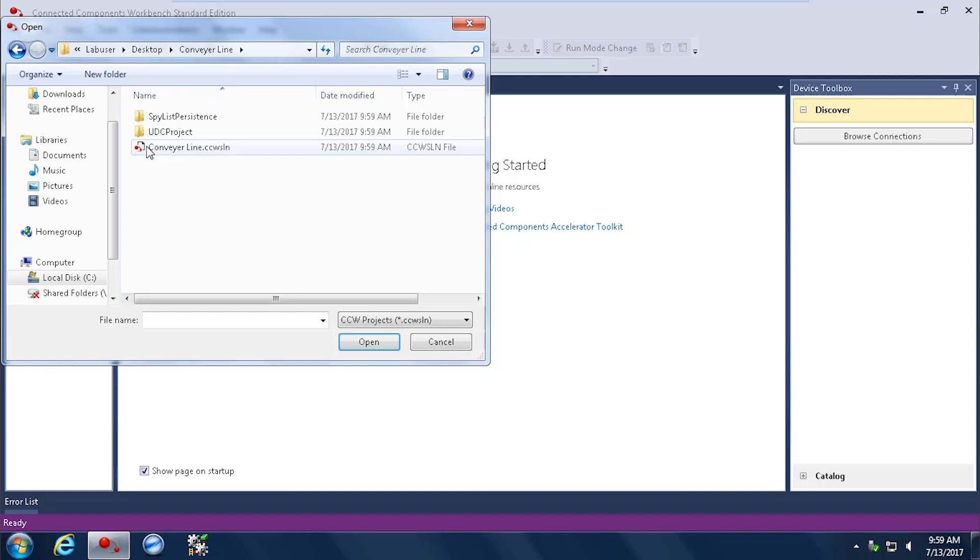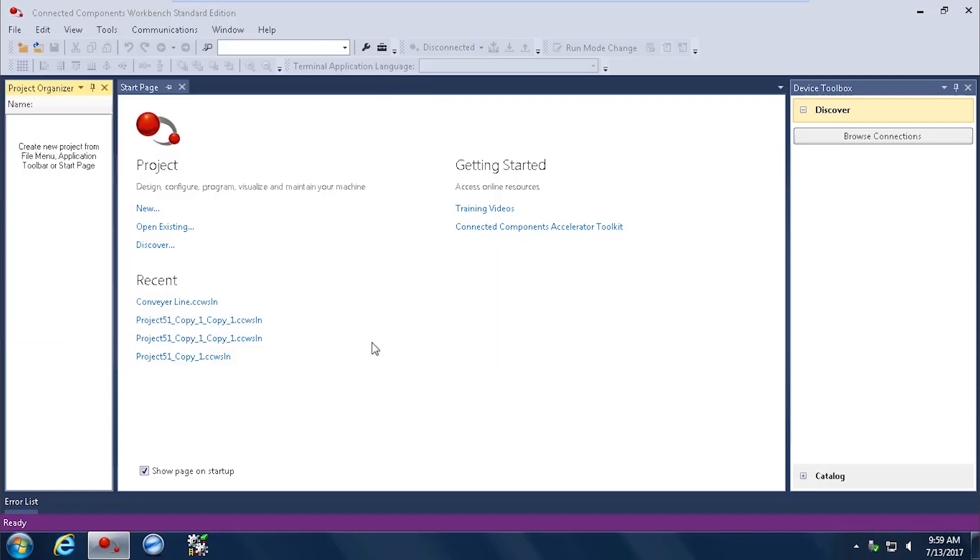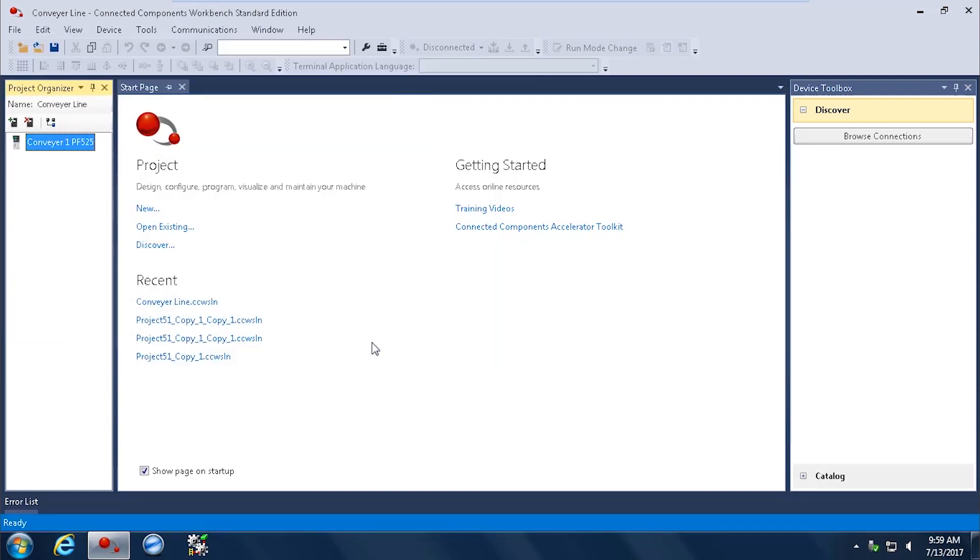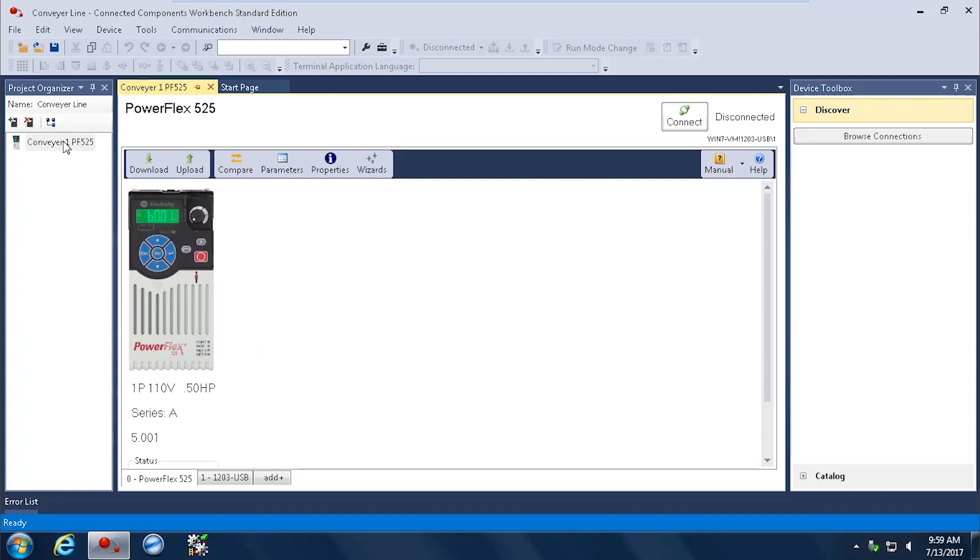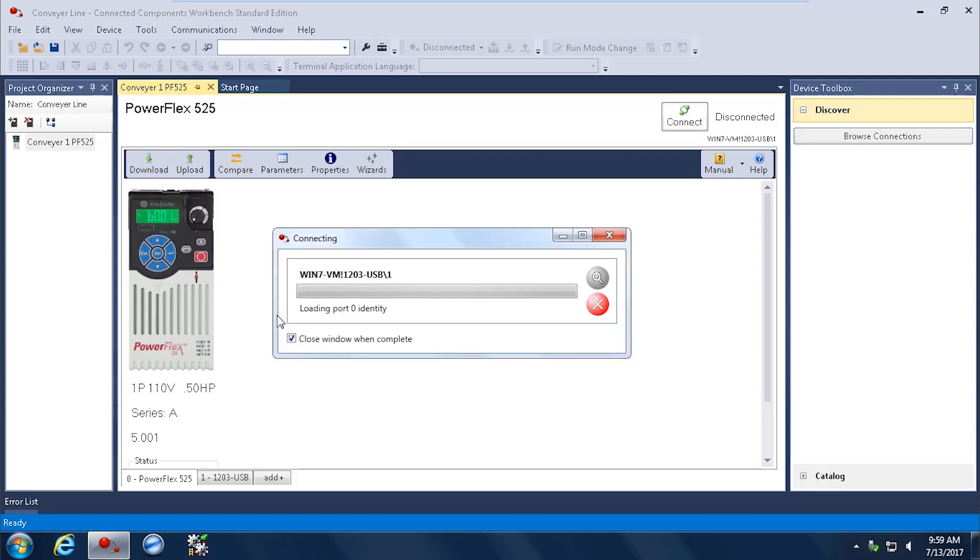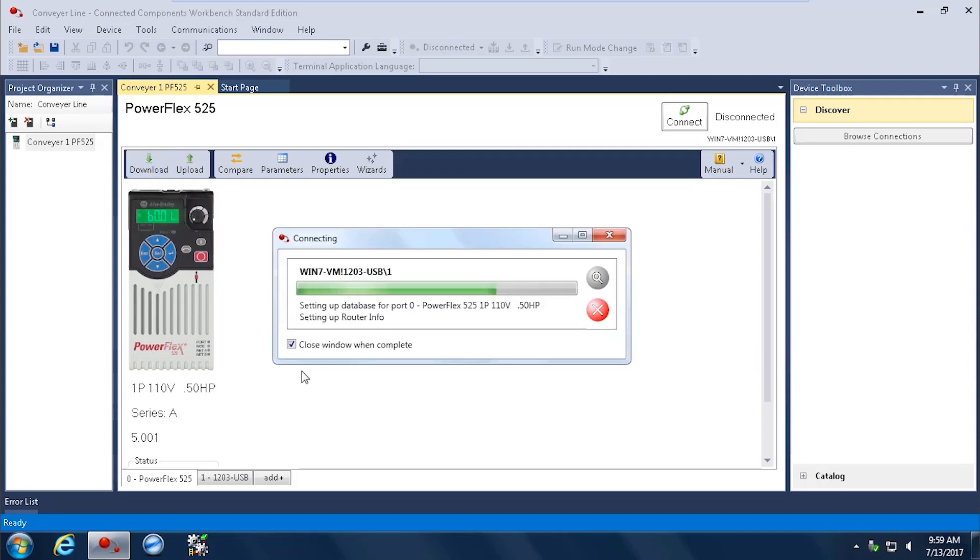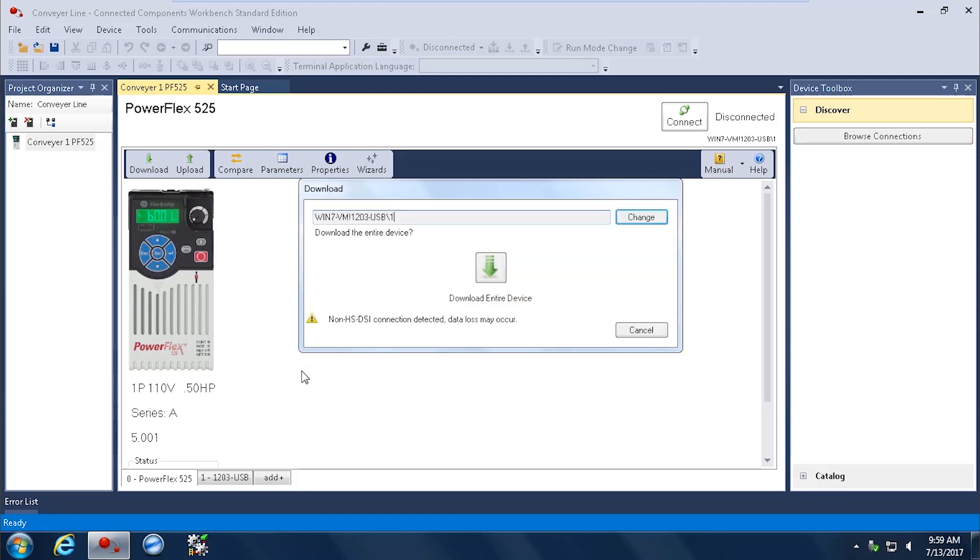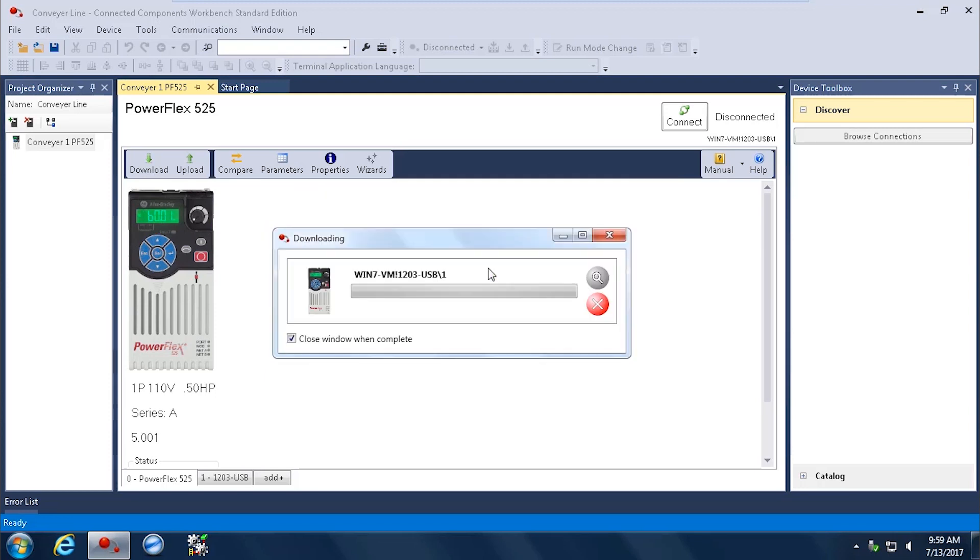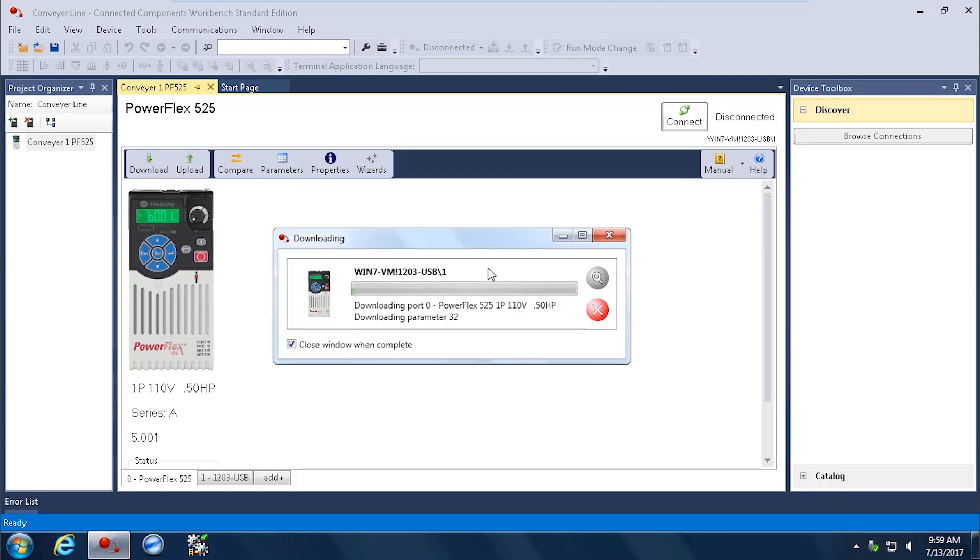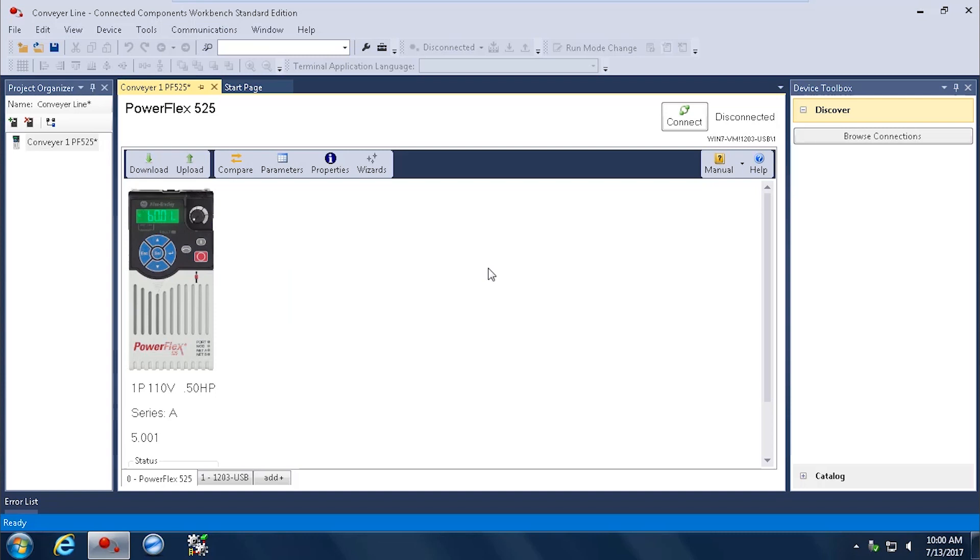And you can see my drive is there in my project Conveyor Line. I could have 10 drives in here. I could have 20 drives. In this case, I only have my one. And it's Conveyor 1 PF525 is the name of this drive. And I'm going to go ahead and download to this new drive that I've just put in. I am now connected to my new drive and I go ahead and download. And I'm going to go ahead and download the entire device. My drive is now finished downloading.